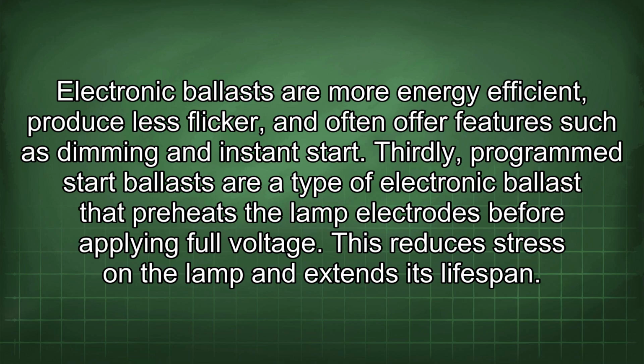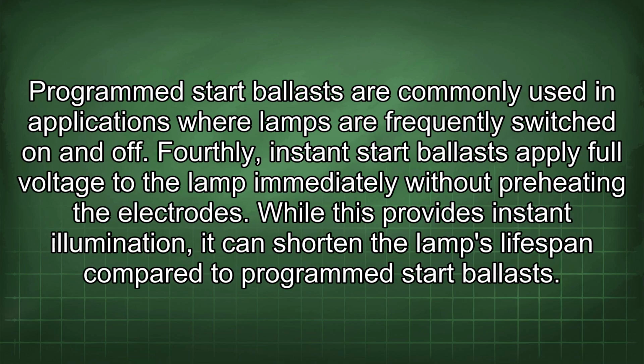Thirdly, programmed start ballasts are a type of electronic ballast that preheats the lamp electrodes before applying full voltage. This reduces stress on the lamp and extends its lifespan. Programmed start ballasts are commonly used in applications where lamps are frequently switched on and off. Fourthly, instant start ballasts apply full voltage to the lamp immediately without preheating the electrodes. While this provides instant illumination, it can shorten the lamp's lifespan compared to programmed start ballasts.